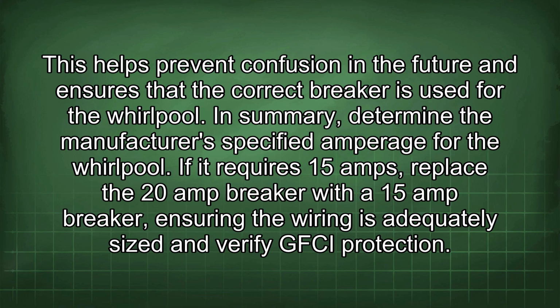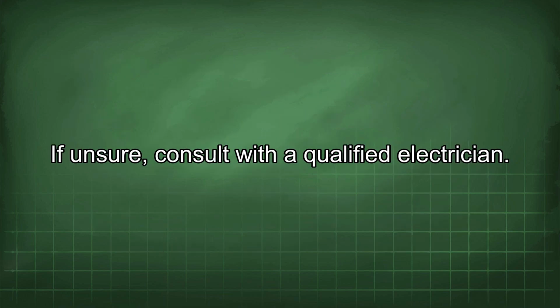In summary, determine the manufacturer's specified amperage for the Whirlpool. If it requires 15 amps, replace the 20 amp breaker with a 15 amp breaker, ensuring the wiring is adequately sized and verify GFCI protection. If unsure, consult with a qualified electrician.